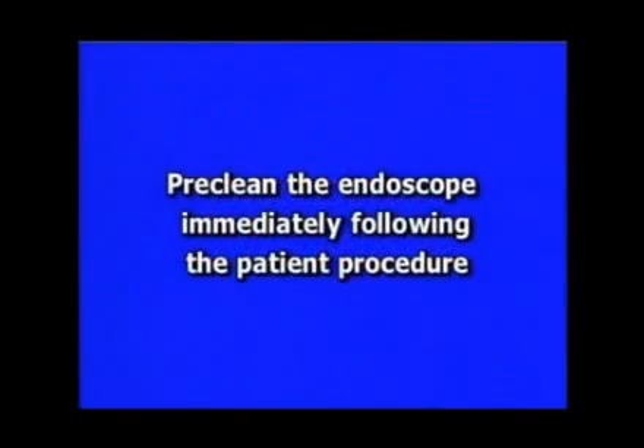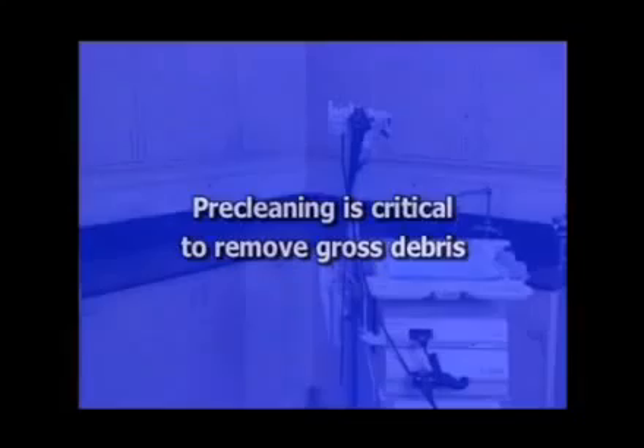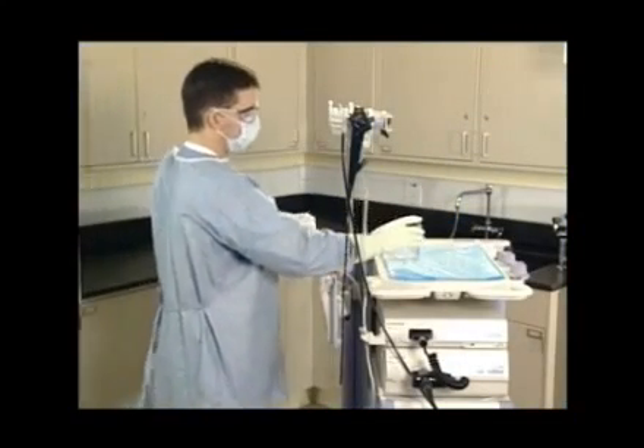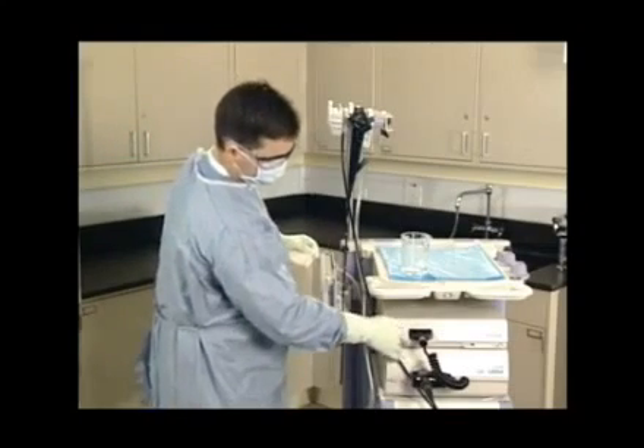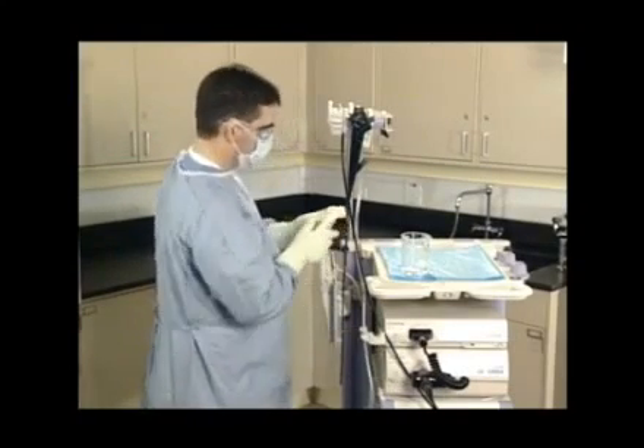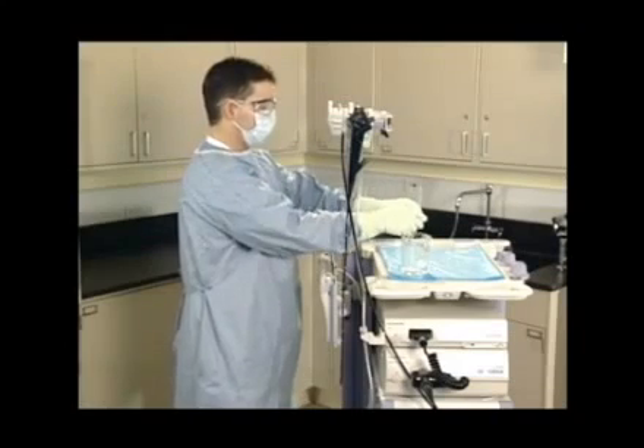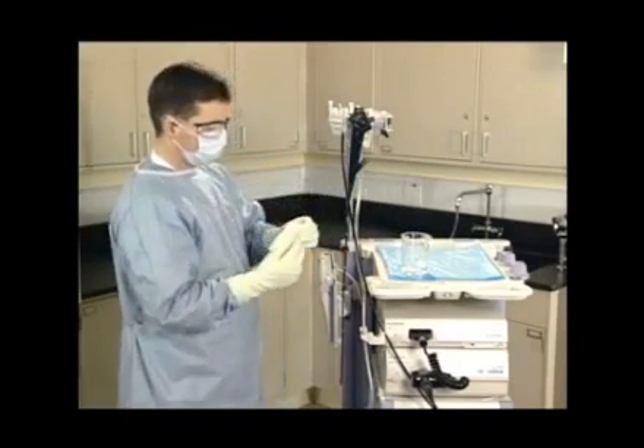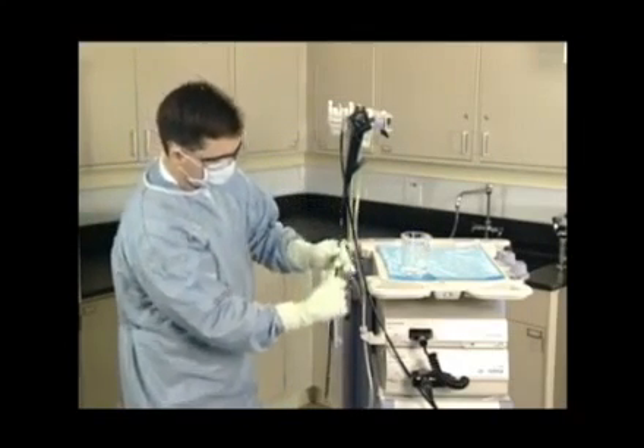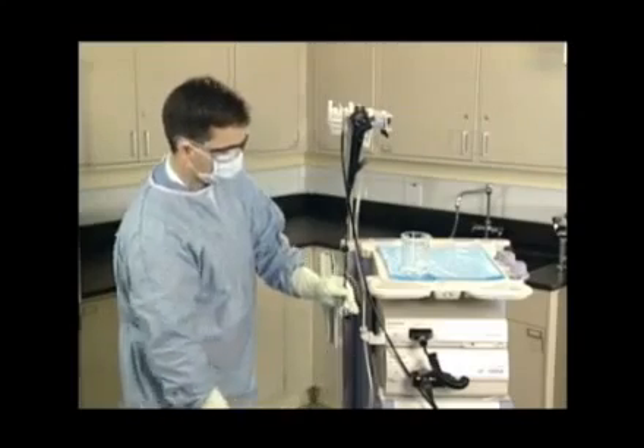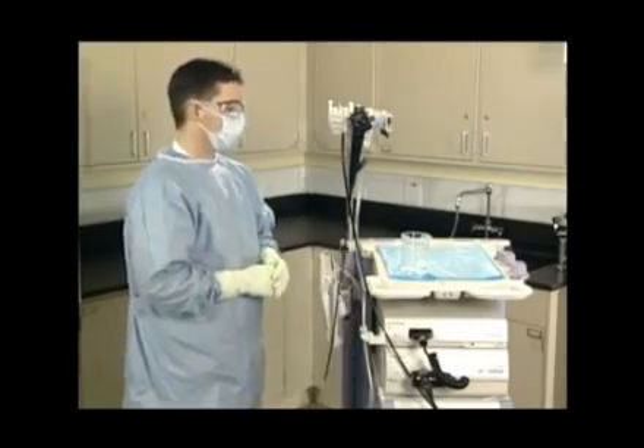Pre-cleaning is the first reprocessing step and is performed at the bedside immediately after the patient procedure. Pre-cleaning is critical to remove gross patient debris from the bronchoscope before it has a chance to dry. For pre-cleaning, you will need a 500 milliliter container of detergent solution nearby. First, turn off the video processor and light source. Then, gently wipe the bronchoscope insertion tube from the control section to the distal tip, using a lint-free cloth or sponge soaked in detergent solution.